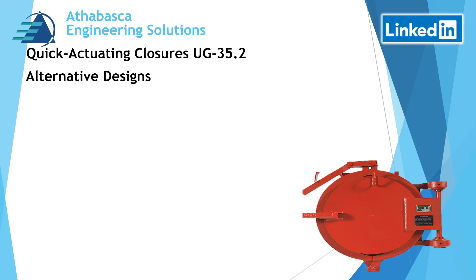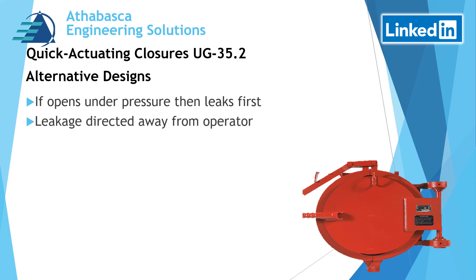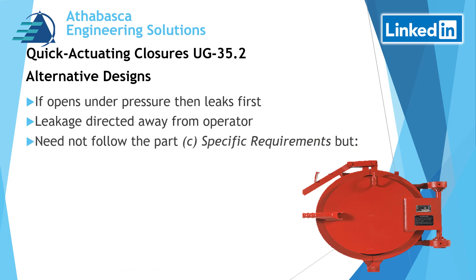UG35.2 also covers alternate designs. If the closure opens under pressure, then it must leak first. Leakage must be directed away from the operator. This alternate design does not need to follow the specific Part C requirements described previously.